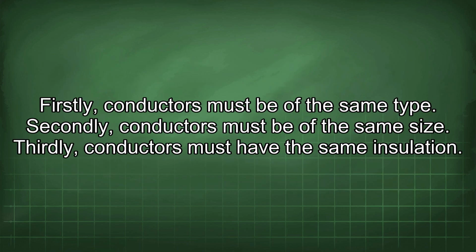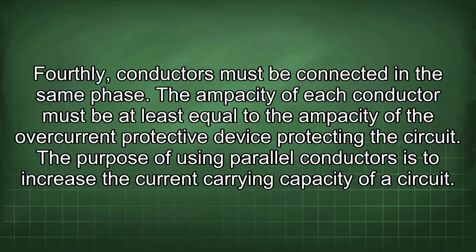Firstly, conductors must be of the same type. Secondly, conductors must be of the same size. Thirdly, conductors must have the same insulation. Fourthly, conductors must be connected in the same phase.